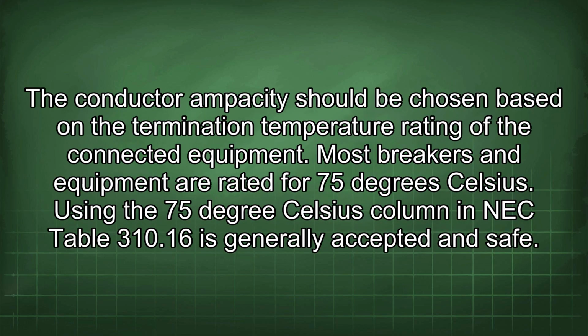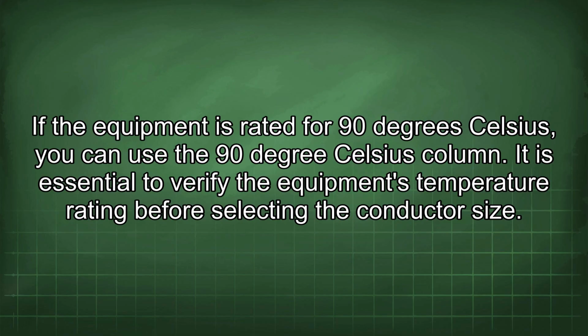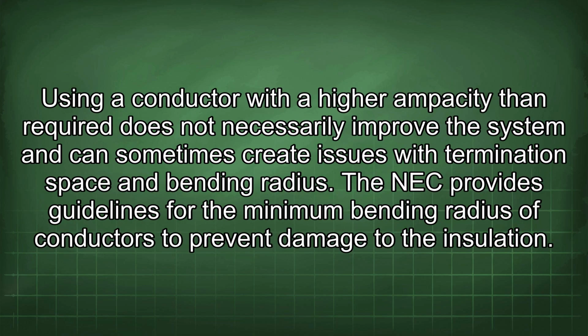The conductor ampacity should be chosen based on the termination temperature rating of the connected equipment. Most breakers and equipment are rated for 75 degrees Celsius. Using the 75 degrees Celsius column in NEC Table 310.16 is generally accepted and safe. If the equipment is rated for 90 degrees Celsius, you can use the 90 degrees Celsius column. It is essential to verify the equipment's temperature rating before selecting the conductor size. Using a conductor with a higher ampacity than required does not necessarily improve the system and can sometimes create issues with termination space and bending radius.